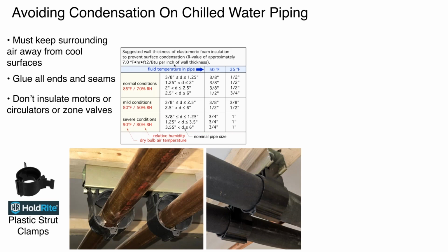But if you look at that copper pipe, you'll see inside that clip, there's actually little ribs that mechanically support the pipe and keep it concentric with the outer ring, and that allows you to slide this insulation right in. And what you don't see here, the final step would be to take a silicone caulk and just put a nice fillet where that insulation comes into that clip. So you've got basically an airtight seal there, and you're not going to get condensation.